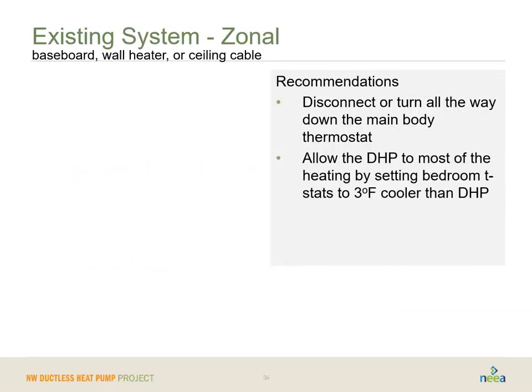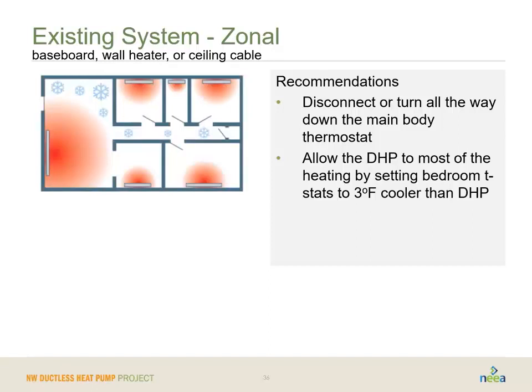So if your existing system is zonal, right? This is the picture we looked at here. You want to turn down the thermostat all the way down in the main body. All the way down means lower than 60 degrees if it has a setting that goes down that far. A lot of them can go down to 55 degrees. If it just says low versus high, then switch it to low. That's going to allow the ductless heat pump head to do the heating in that main body in all instances except for something cataclysmic where the ductless heat pump breaks.